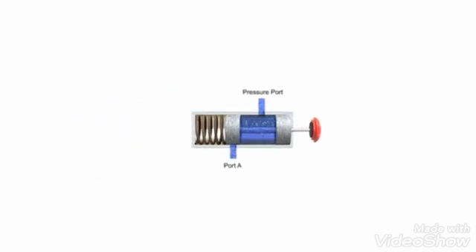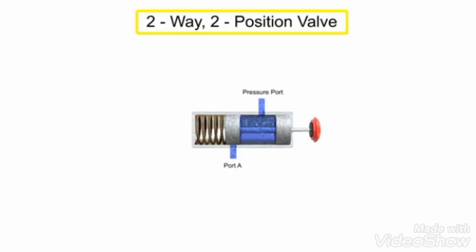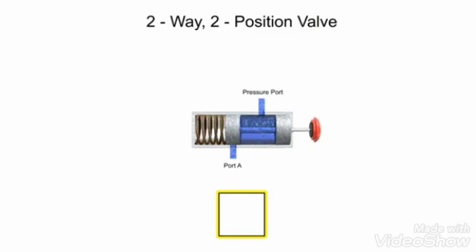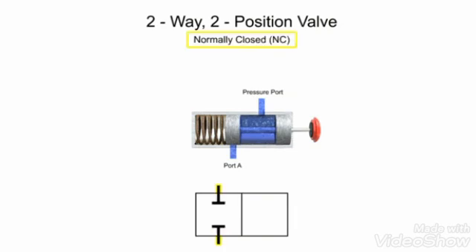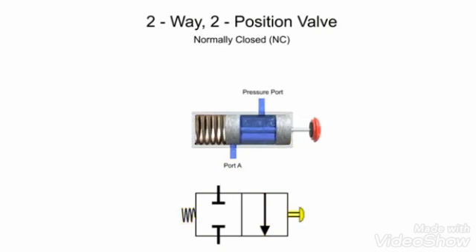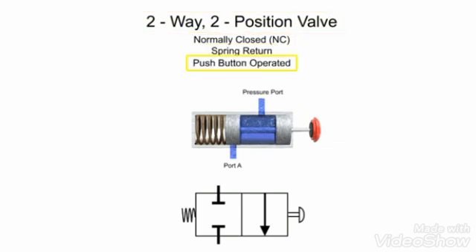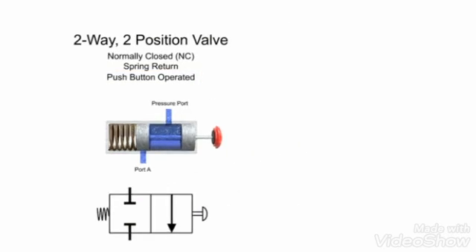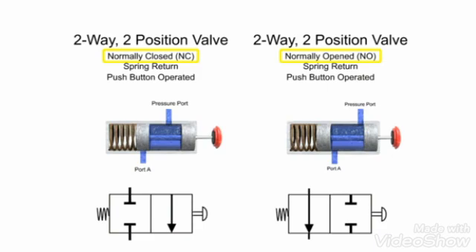Here is a similar valve to the one previously shown. It has two ports and two positions, so it is also a two-way, two-position valve. However, in the normal non-actuated position, both ports are blocked. Therefore, it is a normally closed valve. When the valve is actuated, fluid is allowed to flow from the pressure port to port A. A spring returns the valve to its normally closed position and a push button actuates it to the open position. Therefore, this valve is a two-way, two-position, normally closed, spring return, push button operated valve. While it is similar to the previous example, the differences in the normal position make it a distinctly different valve.